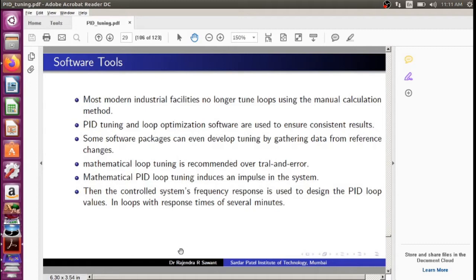One can also have software to find out the control plant from experimental data. The automation system carries out the experiments by a step change in the reference set point, observing the PV without any controller, and by studying the graph, one can choose a systematic method to get the desired PID controller.